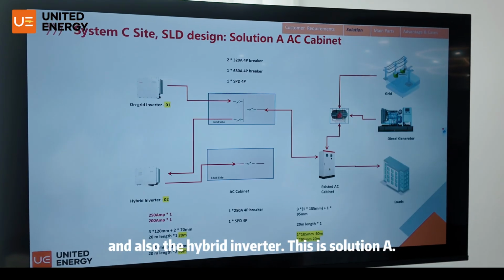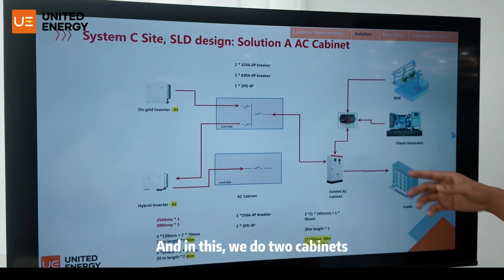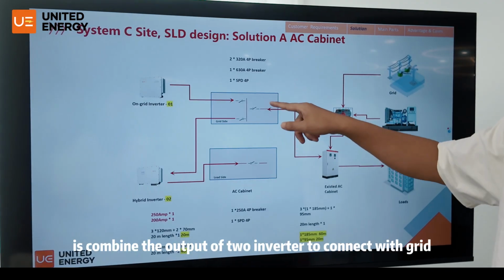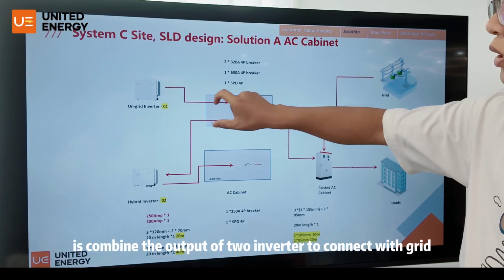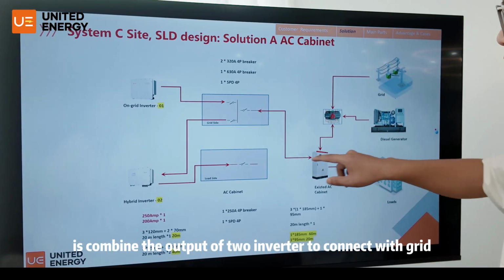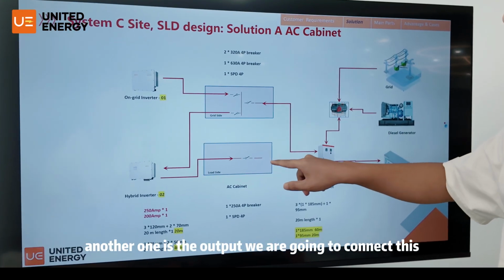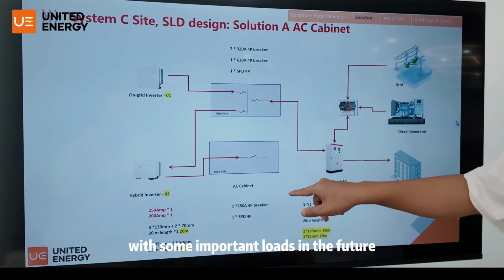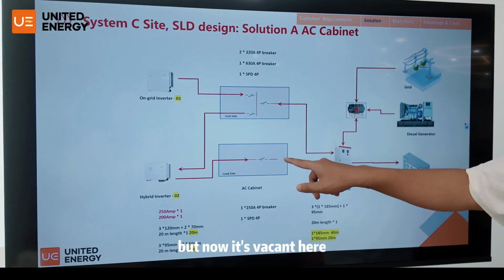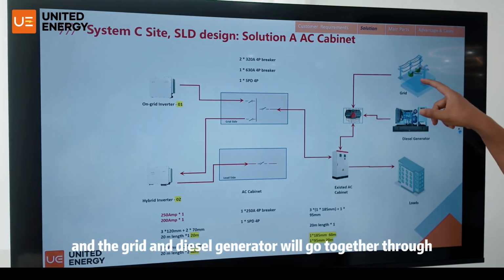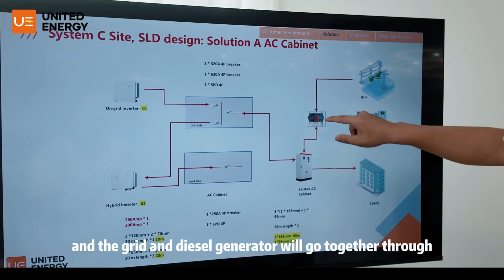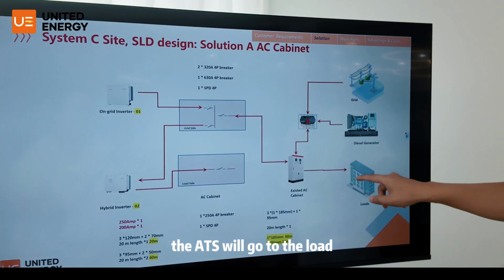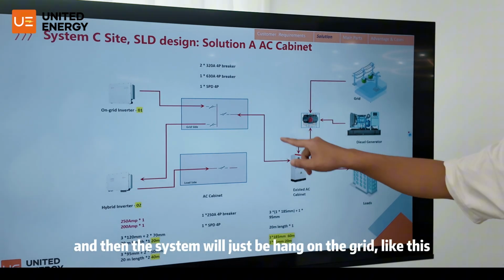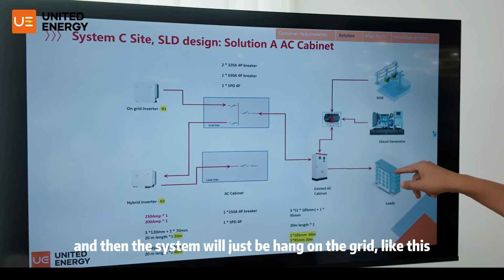This is solution A. In this, we do two cabinets. One cabinet combines the output of two inverters to connect with the grid. Another one is the output that we are going to connect with some important load in the future, but for now it's vacant. The grid and the diesel generator go together through the ATS to the load. And then the system will just be hung on the grid, like this.